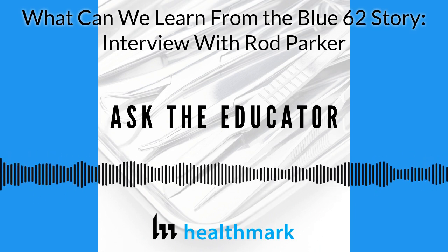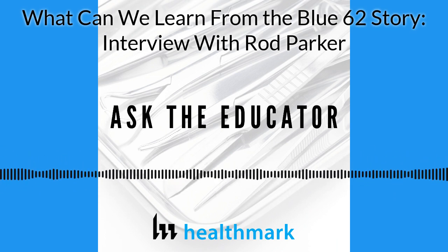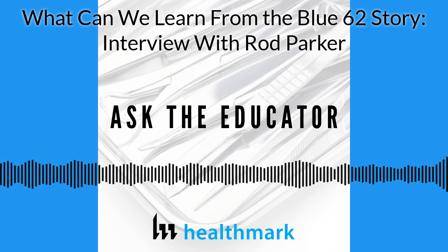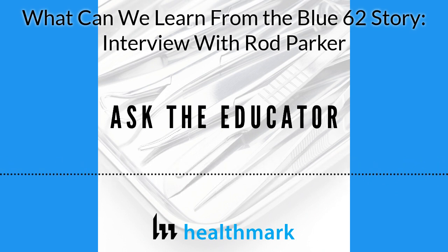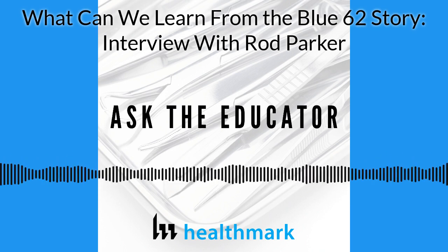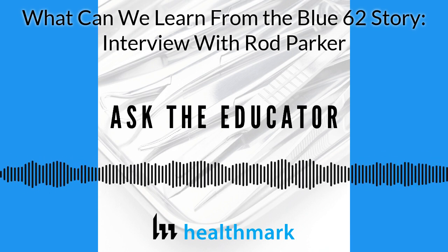It's easy to tell somebody to just rinse longer, so I tell this to my engineers. They say we just have to rinse it for a minute, and I hand them a product and say start rinsing. They rinse for about 10 seconds and start to stop. Then imagine someone in your SPD department having to rinse every one of these pieces for a minute or two — 60 pieces in a set — and next thing you know, you're rinsing for an hour. No one has time to do that.